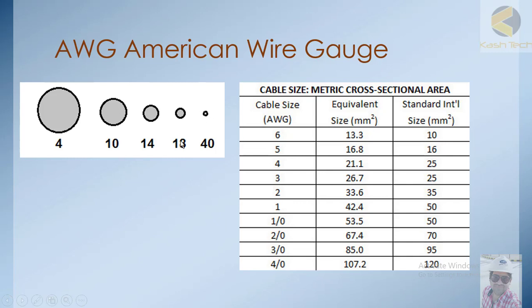If you get a higher AWG number, the cable size is smaller and it carries less current. For example, starting with AWG 6: AWG 6 is equivalent to 13.3 mm² and the internationally available standard size is 10 mm².